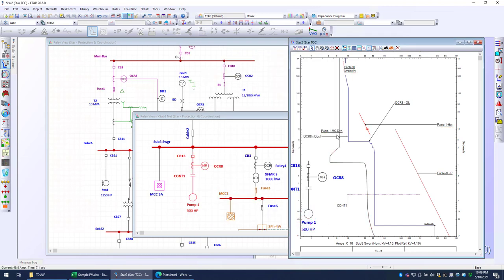This is coming from the actual study that we just performed. So I'm going to click OK, and we get to see the actual dynamic starting curve for this particular motor. So it's based on what we did. You can see here how the motor begins to ramp up, partially loaded.